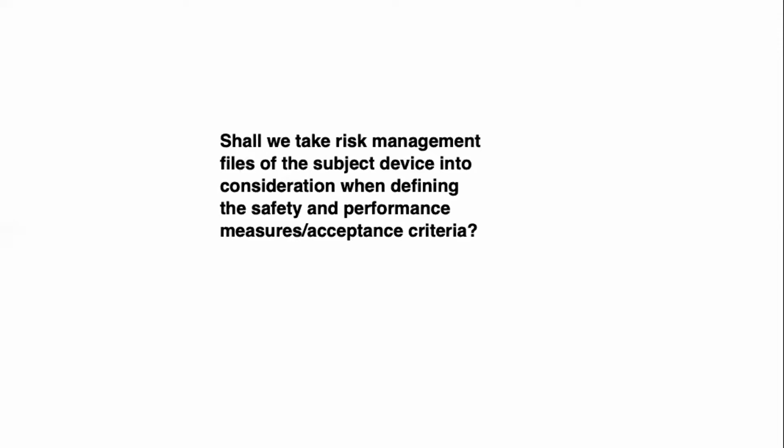I think that's an important point to make that some clients are not clear on, that they don't necessarily demonstrate that their risk management documentation is updated as a part of the evaluation, if necessary, as a part of the evaluation of the device, the clinical evaluation process.